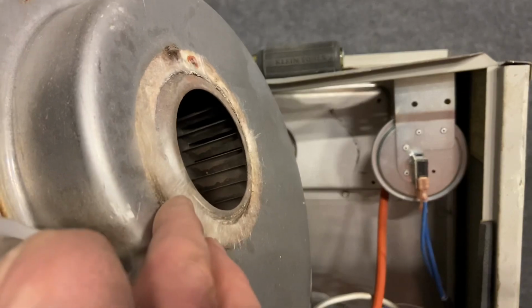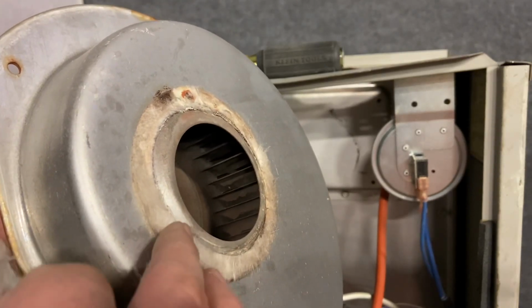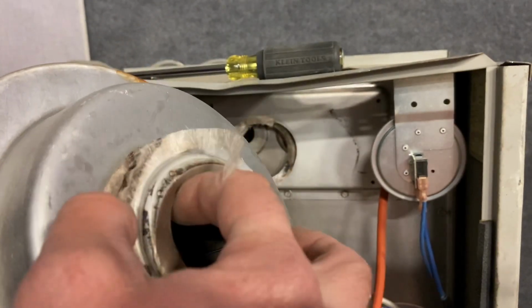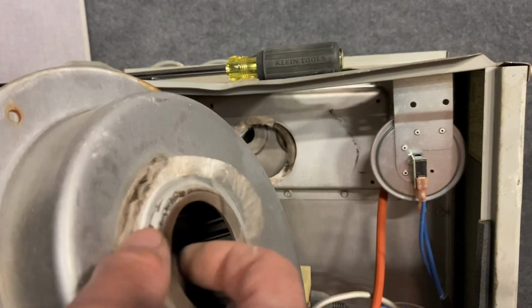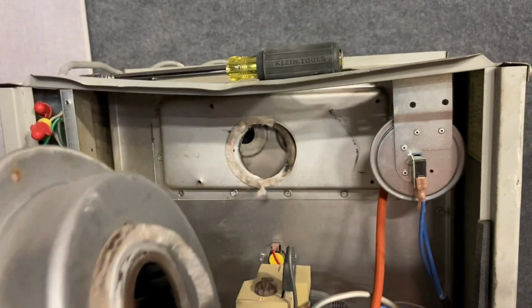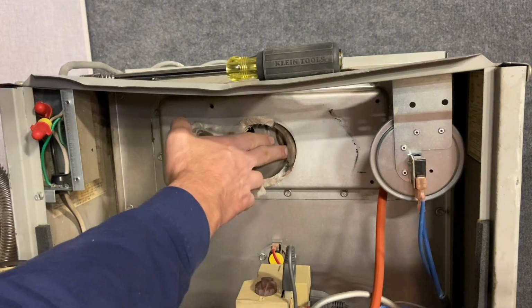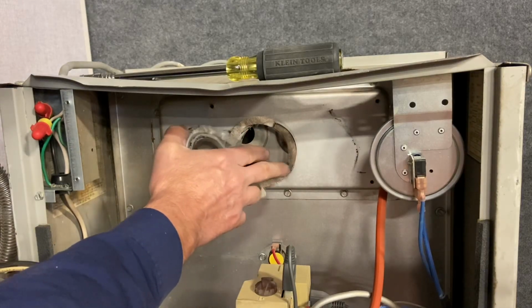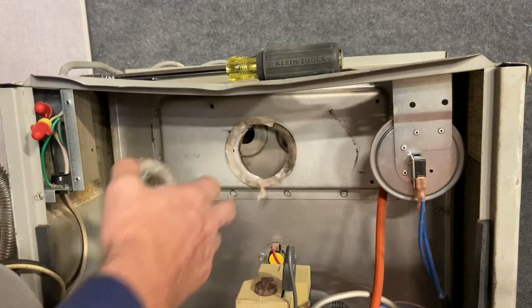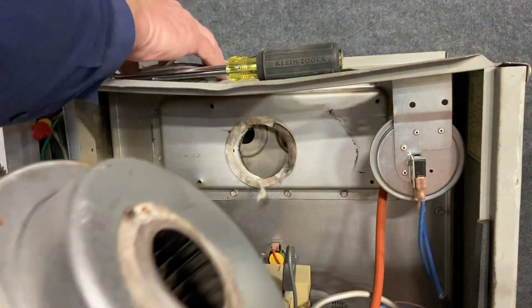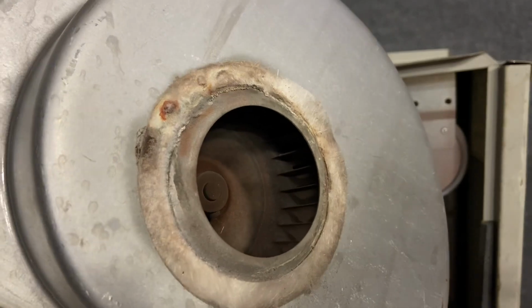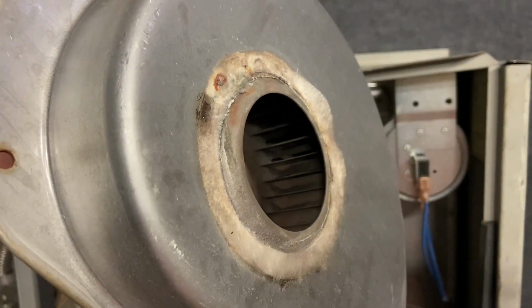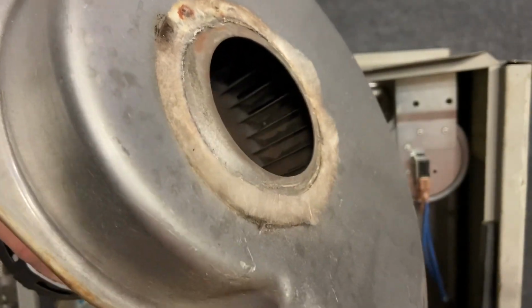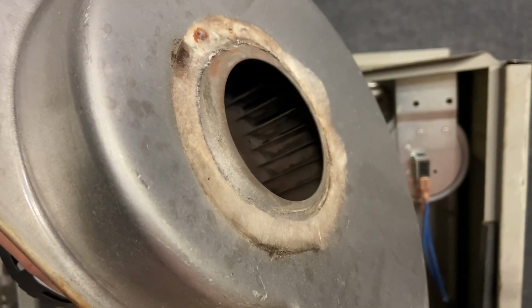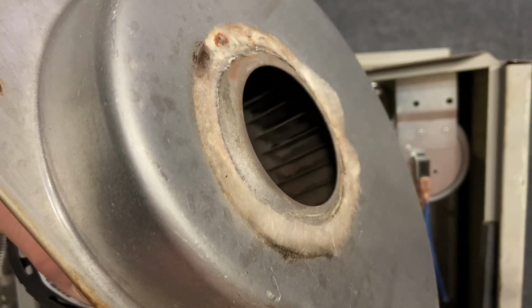Notice also this material here is a gasket material. It's a high temperature fiberglass gasket material. So if I was to take this off, I would have to replace that gasket material before I'd put it back on. And you can see also how it's another gasket here on this side. And you see this burnt mark on here. I don't think the gasket was installed correctly to begin with. Also, if we look inside, we can see a significant amount of rust on this blower wheel. And it's just from age. There's a lot of carbon built up. It probably wasn't running with the right gas pressure. It probably never had a combustion analysis done on it.